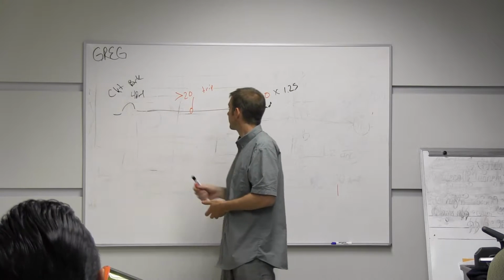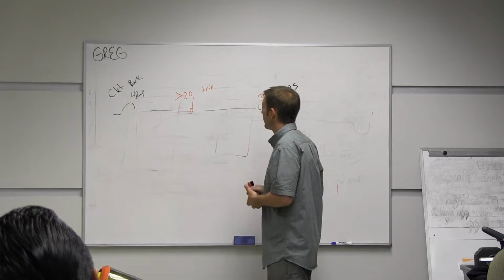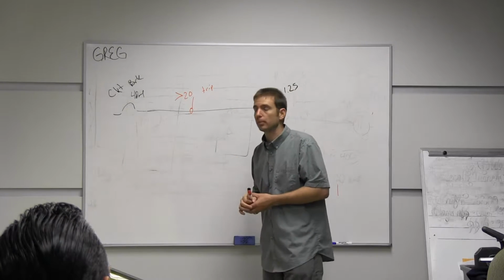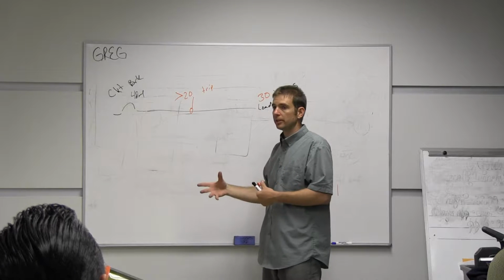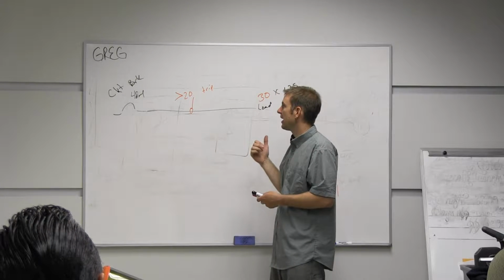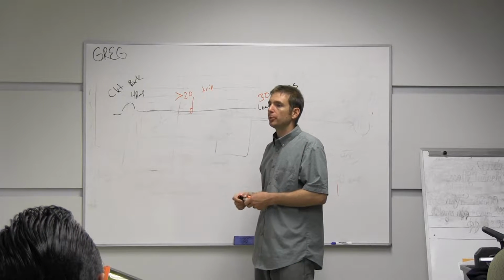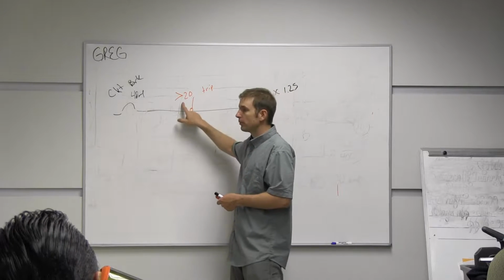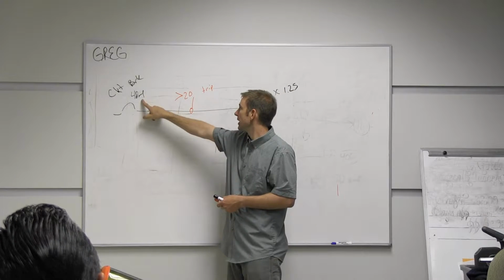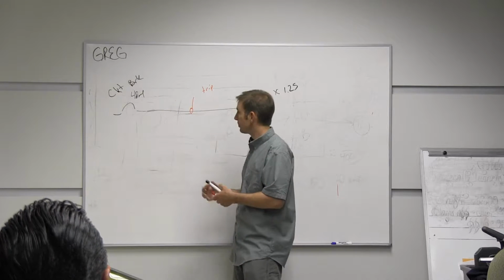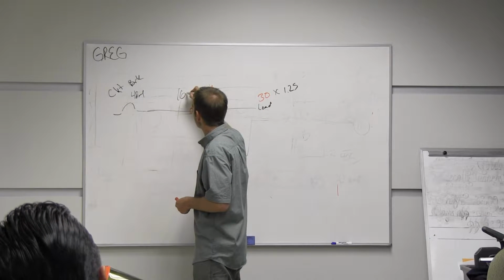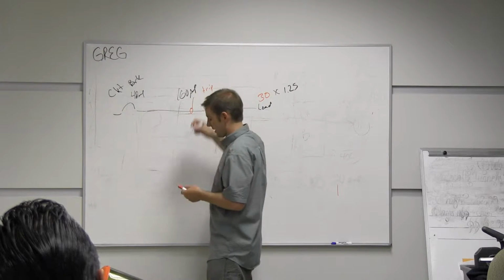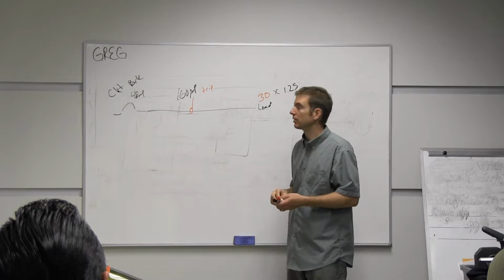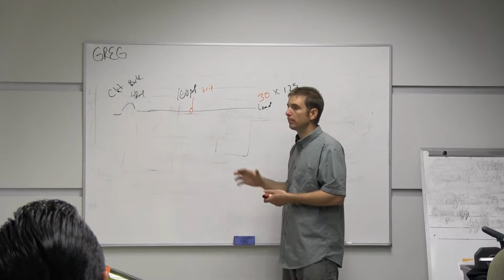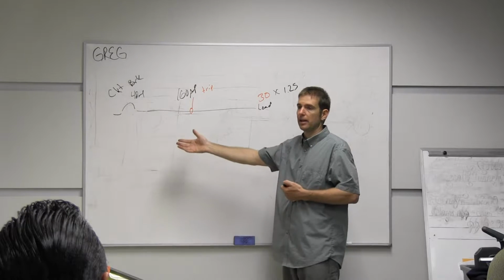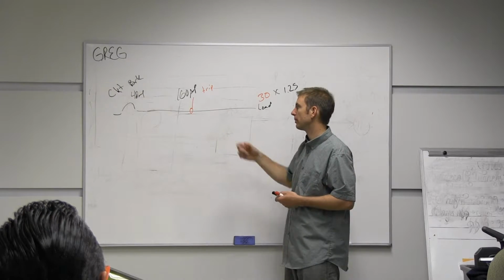So we have a 40 amp circuit breaker. It should be tripping. Now, they trip two different ways. They trip because of an inrush current, which will pull the breaker open, and then they also trip through heat. So if we have a 40 amp breaker and we put 160 amps on it, it's going to trip relatively fast, and it's going to trip from the other method, through that inrush current. It's going to pull that circuit breaker open.